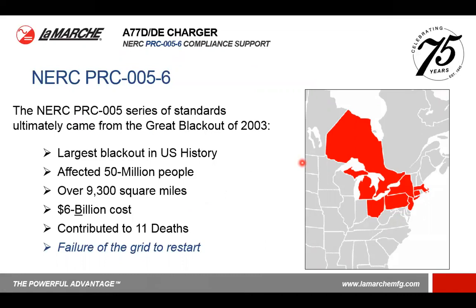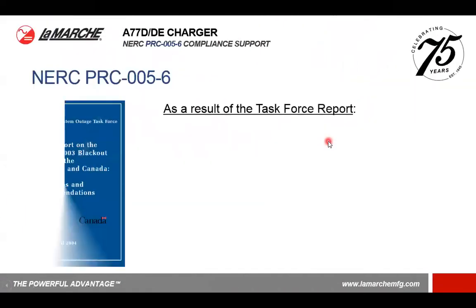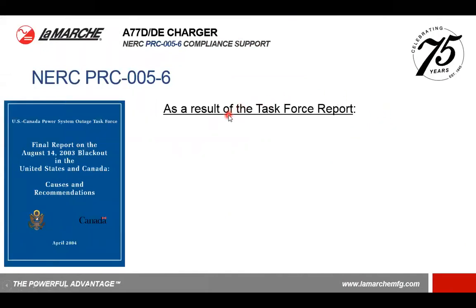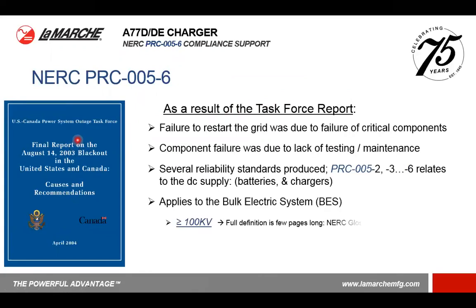Over the period of those 2 days, it wasn't even so much a problem that the grid had failed. It was really a problem that the grid had failed to restart. So from that, FERC decided to have a task force and create a report on what was the cause of the blackout and ultimately the failure to restart. Essentially, the failure to restart the grid was due to failure of critical components. And those critical components had failed, and they established it was really due to lack of testing and maintenance. Early testing could have identified these components as towards their end of life, and this whole situation could have been avoided. So from the task force, several reliability standards were produced.